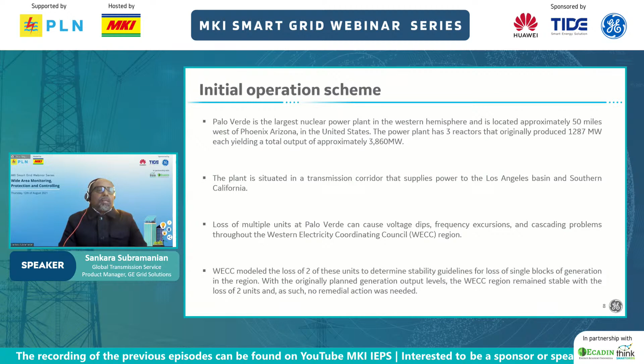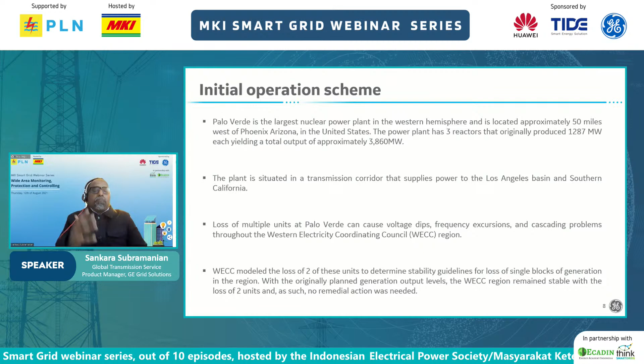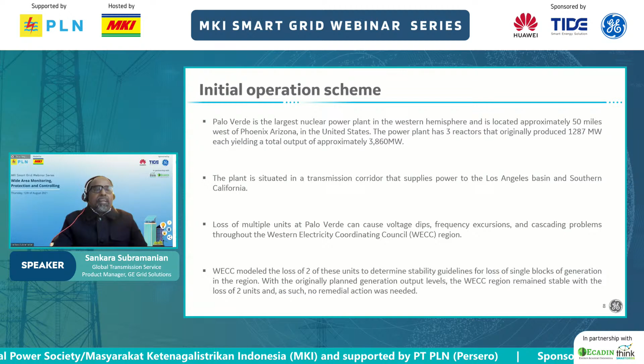Loss of multiple units of Palo Verde can cause voltage dips and frequency excursions. So WECC modeled the loss of 2 of these units to determine, with the stability guidelines, whether there were any issues with the originally planned generation output levels. The WECC region remained stable for the loss of 2 units, and no such remedial actions were needed.